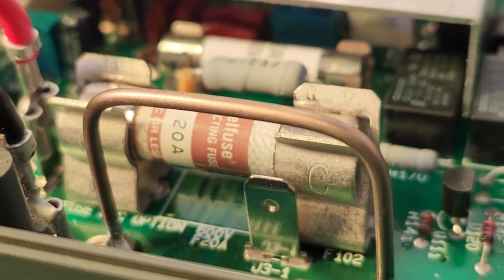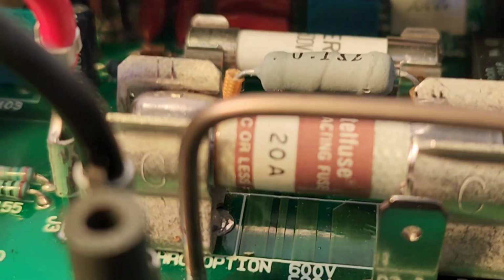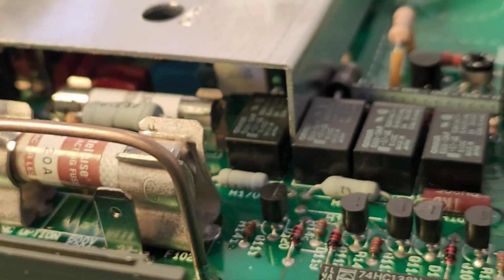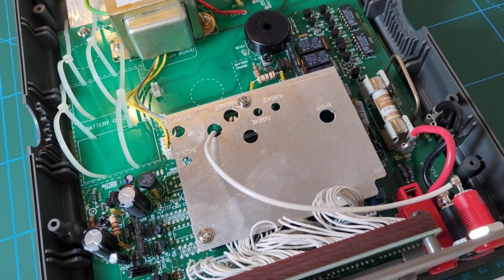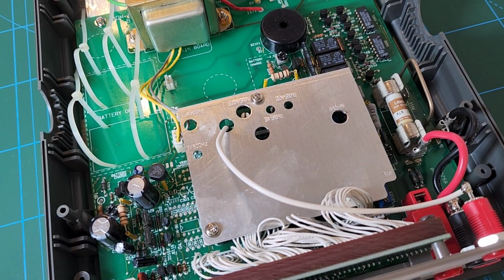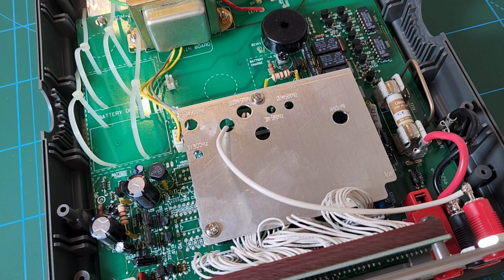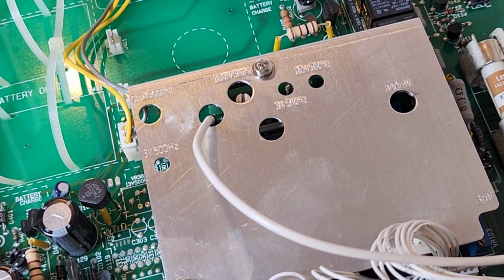I think this is a slightly better angle. You get an overall picture. The size of that shunt, I mean, they were not messing around. And look at that. If calibration was your thing, check it out. If your meter started to drift over time, which in this case, 30 years later, it hasn't, but if it did, you can actually self-calibrate it yourself.